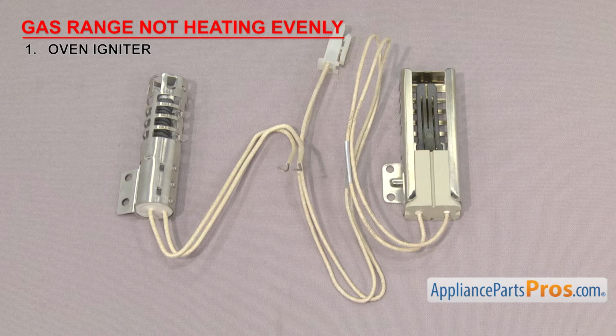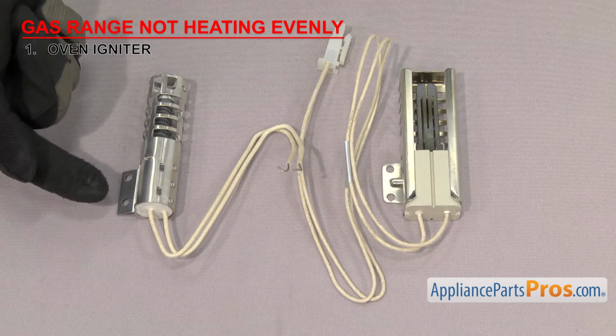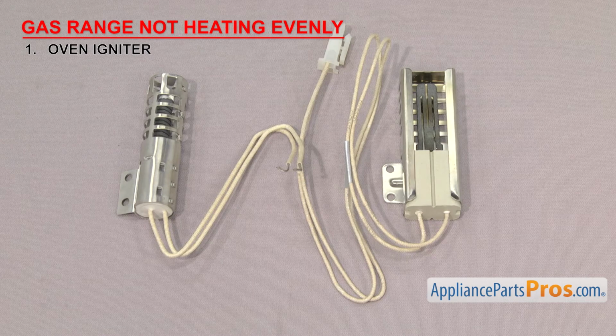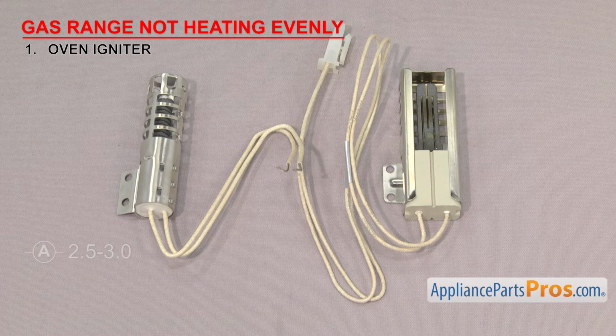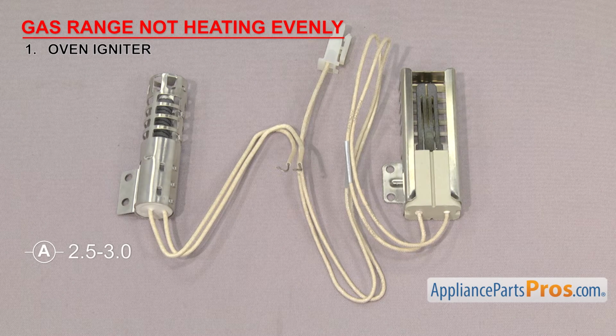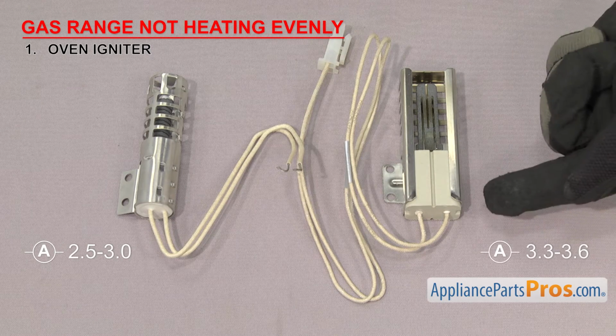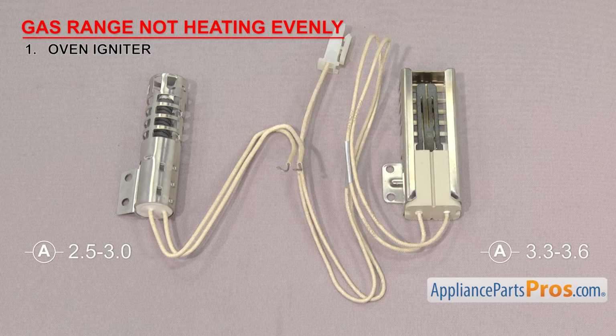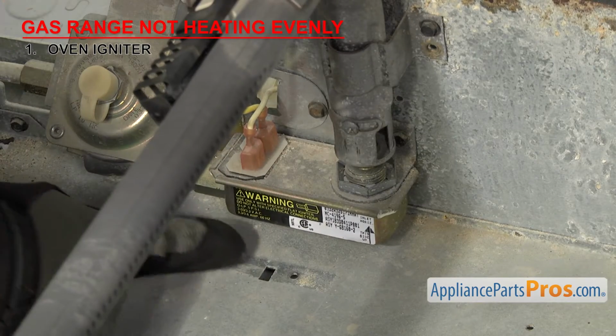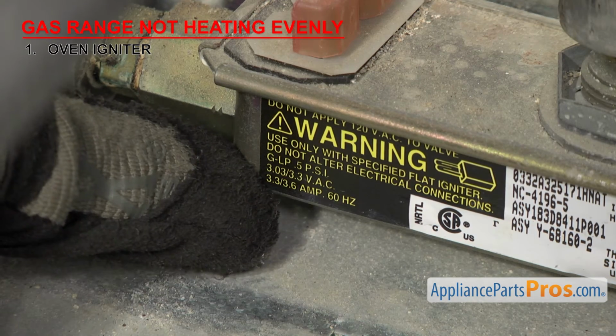There are a few different designs of igniters that are rated at different amps. You have the round igniters and the blue square ones that replace some round igniters. They're used with oven safety valves that are rated at 2.5 to 3 amps. Then you have the regular square igniters that are used with valves rated at 3.3 to 3.6 amps. You can see the amp rating on the oven safety valve itself.